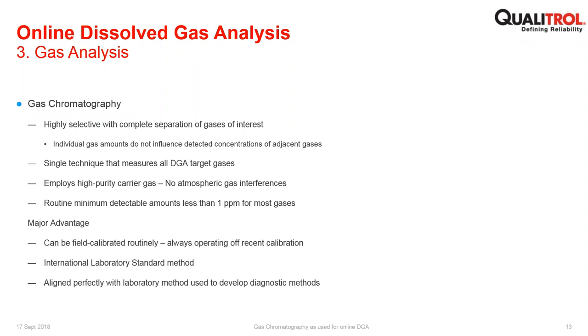Gas chromatography is the international laboratory standard method for the reasons that I've already described. And because all of those diagnostic techniques, Duval triangle and pentagon, which I'll illustrate in the next slide, are all based off data which was collected with gas chromatography, then you have better possibility of alignment. So the data that you're getting from your online system, ultimately, you don't care about ppms, you care about diagnostics. And because this is the same technology as is used in the lab, the possibility for high quality alignment between the diagnostic system and the data that you get from an online GC system is increased.